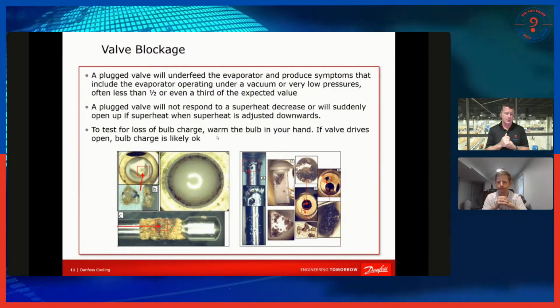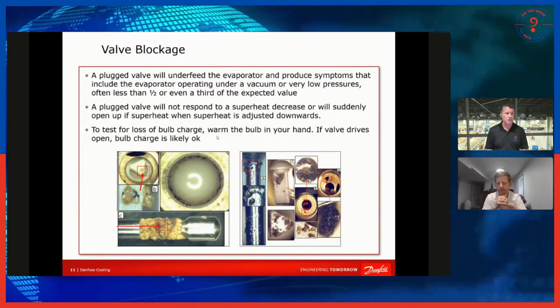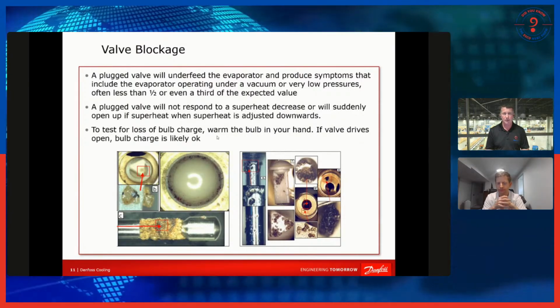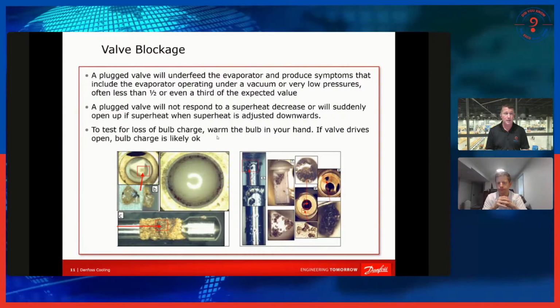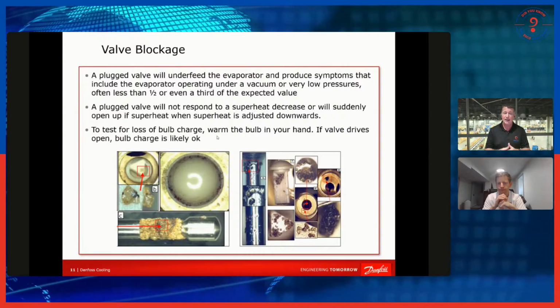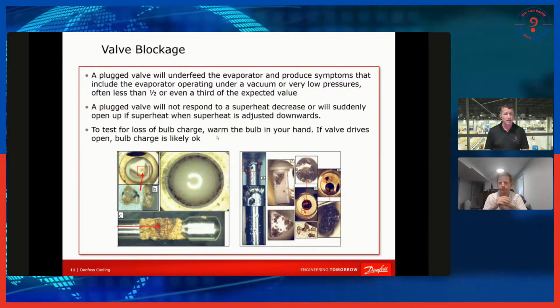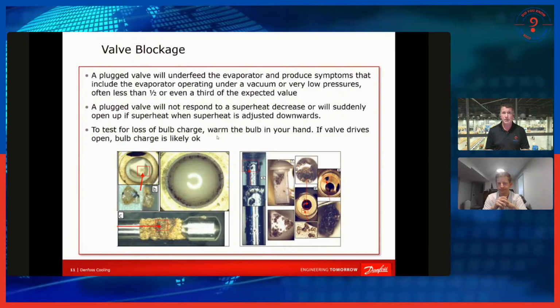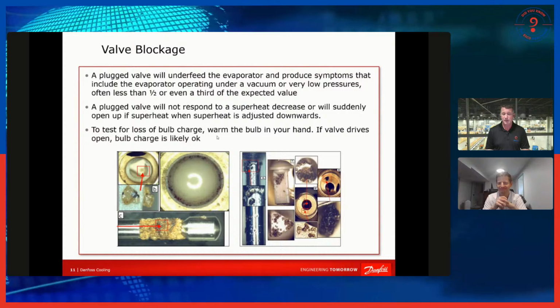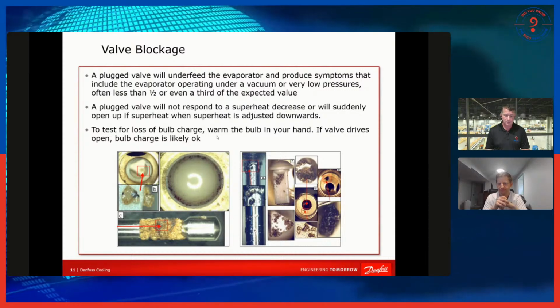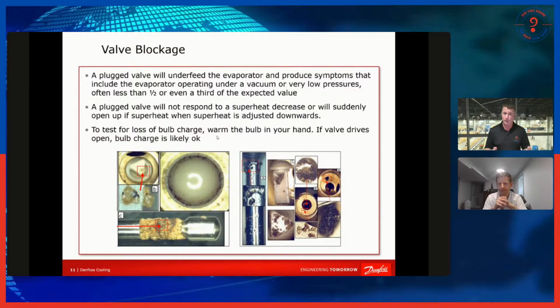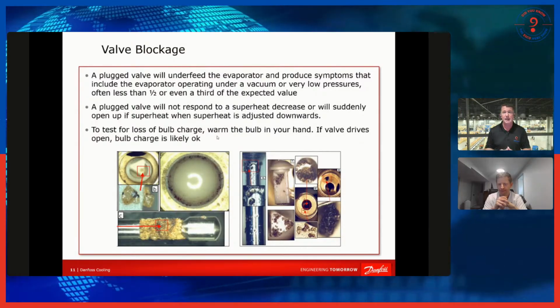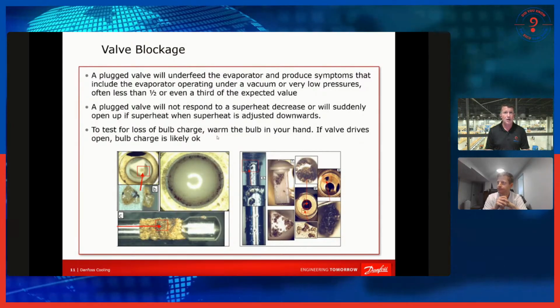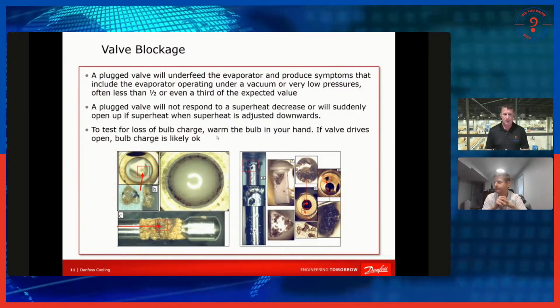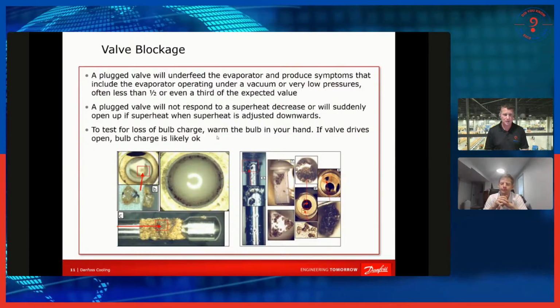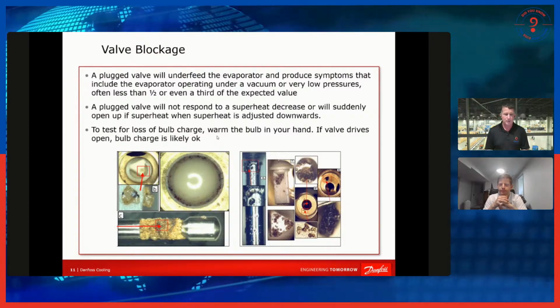Yeah, that's one of the things that I wanted to make sure people are aware of, because if you're used to seeing a screen in front of that metering device, it may not or likely will not be there. I have seen some system designs that have a screen but not a filter dryer. When we start looking at these critically charged and high efficiency systems, the less restriction in the system possible, the better it's going to operate. But on the technical, on the service side, it's important to know that improper installations and repairs can absolutely affect an electronic expansion valve more than it could on that thermostatic expansion valve.